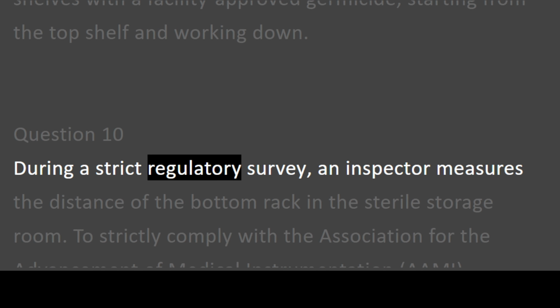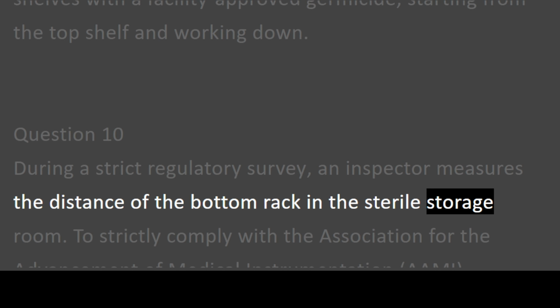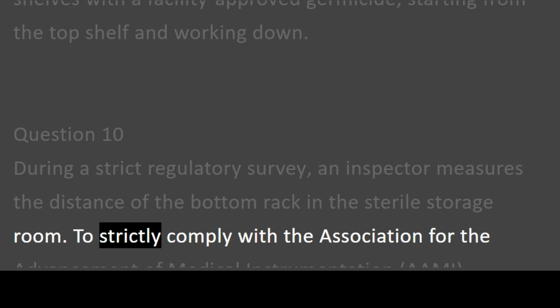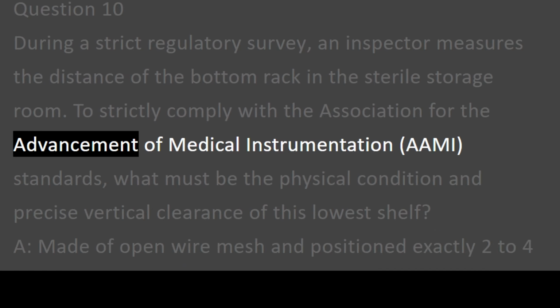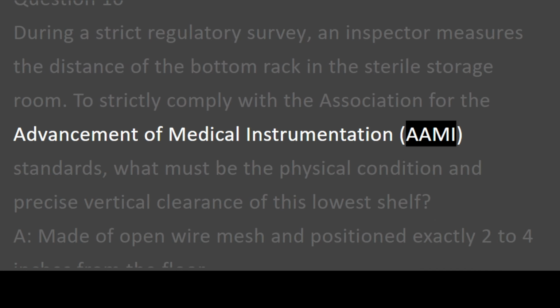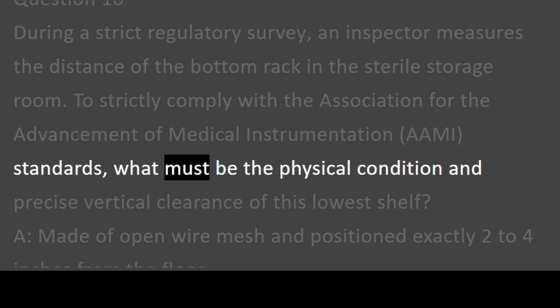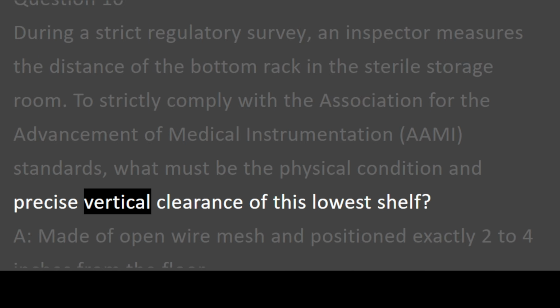During a strict regulatory survey, an inspector measures the distance of the bottom rack in the sterile storage room. To strictly comply with the Association for the Advancement of Medical Instrumentation, AAMI, standards, what must be the physical condition and precise vertical clearance of this lowest shelf?